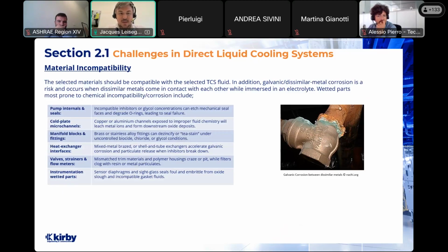This is a particular risk because some cold plates use aluminium as part of their construction, which has a high electrochemical potential difference with things like copper, brass, and stainless steel. And using carbon steel on the piping system also creates that large electrochemical potential difference between the materials. So understanding the different materials within the system is key. Some of the wetted parts that are most prone to chemical incompatibility or corrosion include pump internals and seals, the cold plate microchannels, manifold blocks and fittings, the heat exchanger interfaces, valves, strainers, and flow meters, as well as instrumentation wetted parts.